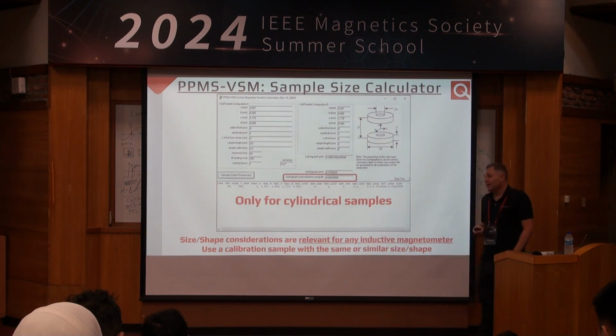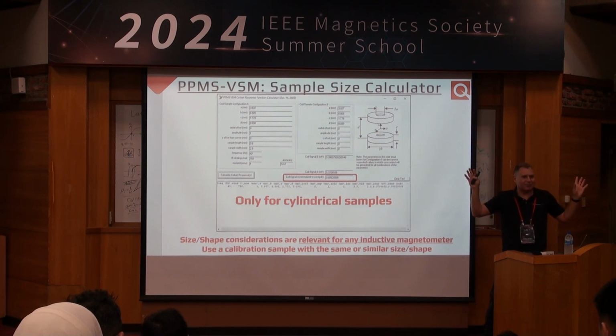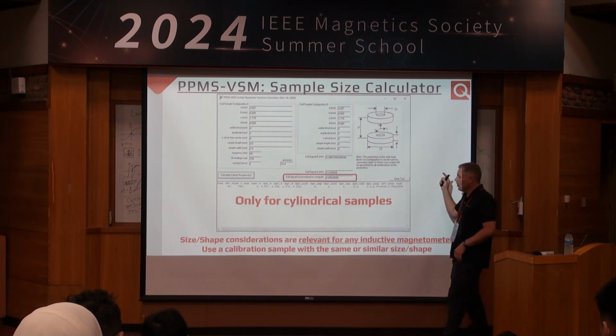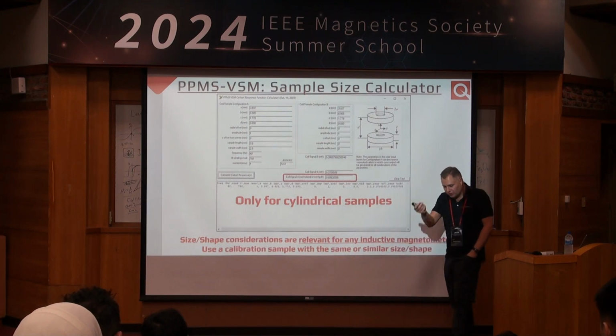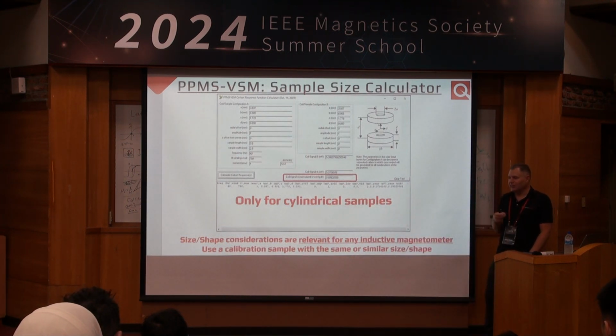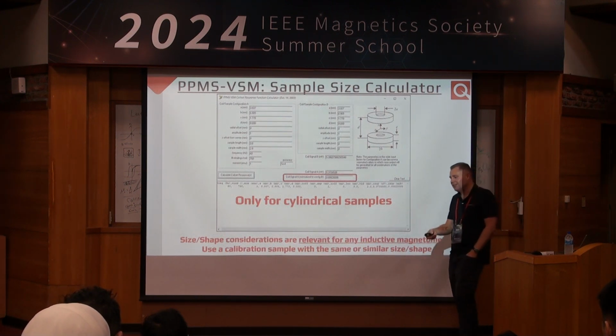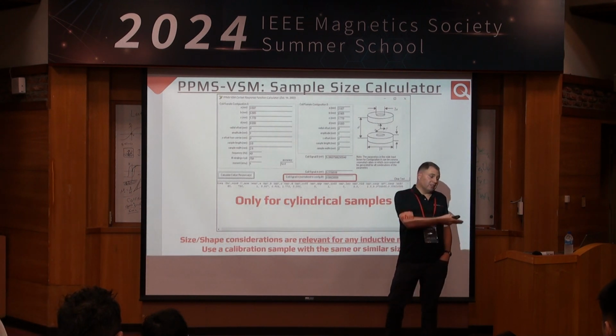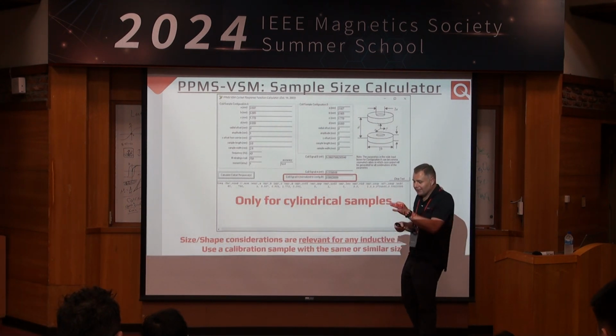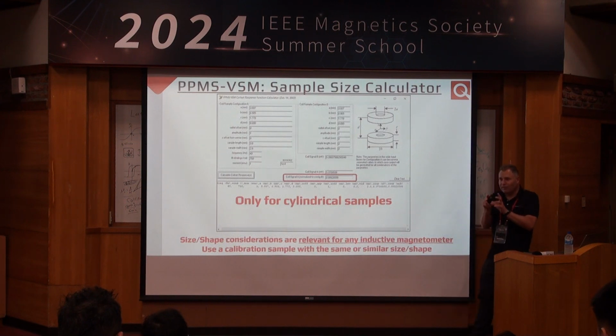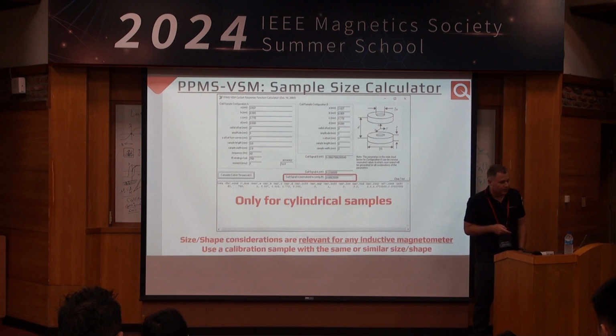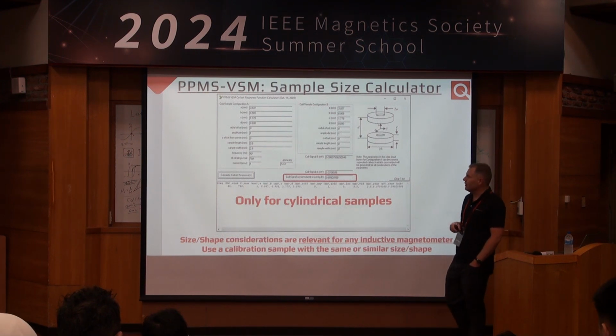These things affect the measurement. Now, if you're like me, when I was a graduate student, all of my hysteresis loops, I just normalized plus minus 1. I didn't care, right? And I understand that's most of you as well. But if you actually care, you have to take these things into account. Let's say you're measuring a thin film, and your advisor says, hey, how thick is that thin film? How do you know? Well, you did X-ray reflectivity, you know the thickness, maybe you did some profilometry. He's like, well, let's also do magnetometry. You go ahead and calculate the saturation moment. You divide by the volume. And it's off. Well, maybe it's because your measurements weren't as accurate as they should have been. So these things need to be taken into account.